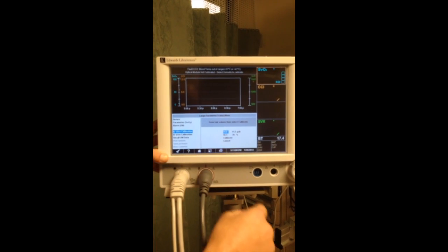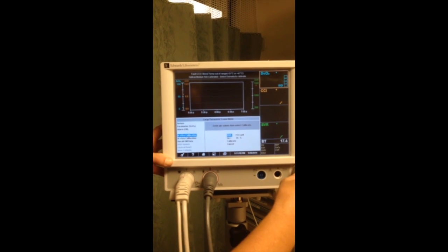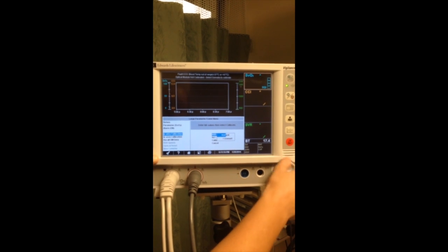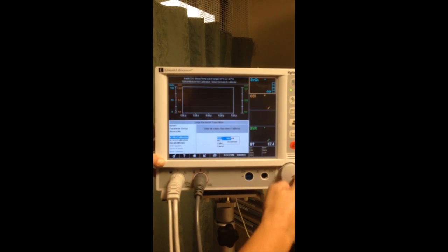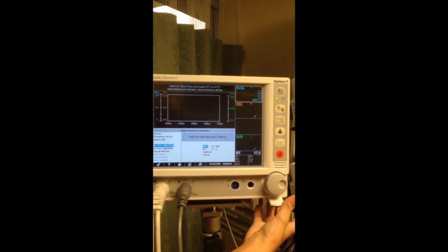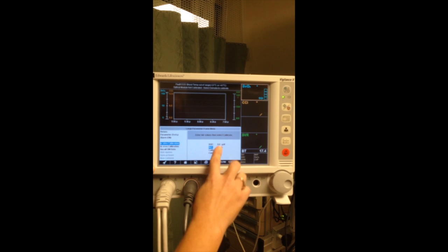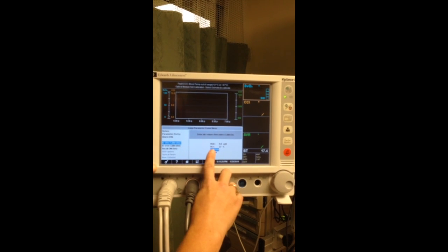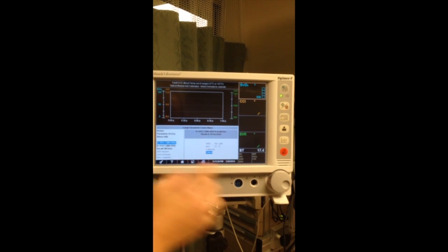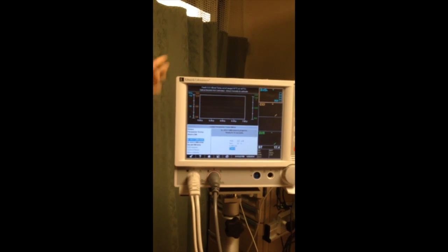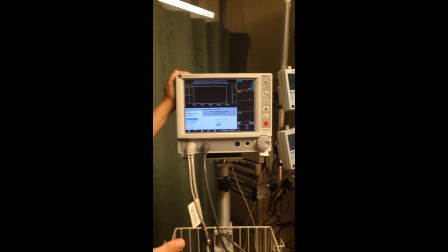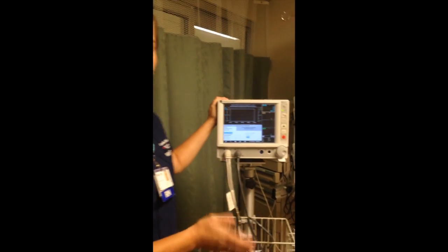Push again. And at that point, you're going to put in your most recent hemoglobin. Even if it's the AM hemoglobin, that's fine. So we'll put in a hemoglobin of 9. You just scroll until you get to where the hemoglobin is and push. Once your lab values are correct, you push on calibrate, and it'll say ready in 20 seconds. As it's counting down, it's doing its own self-test, and then it will say calibration complete.